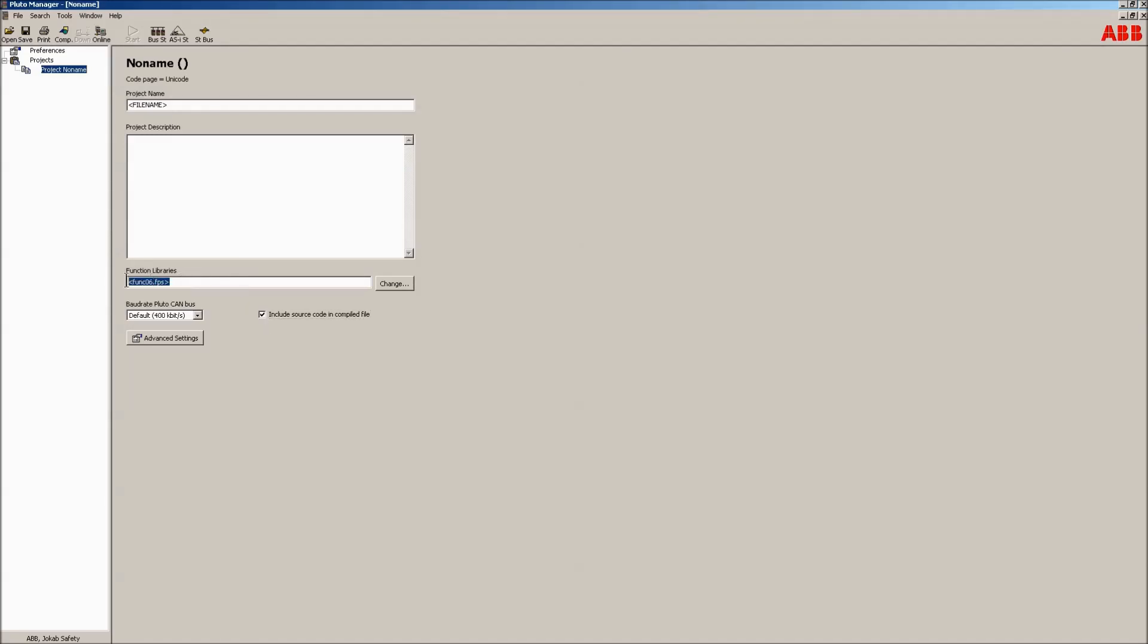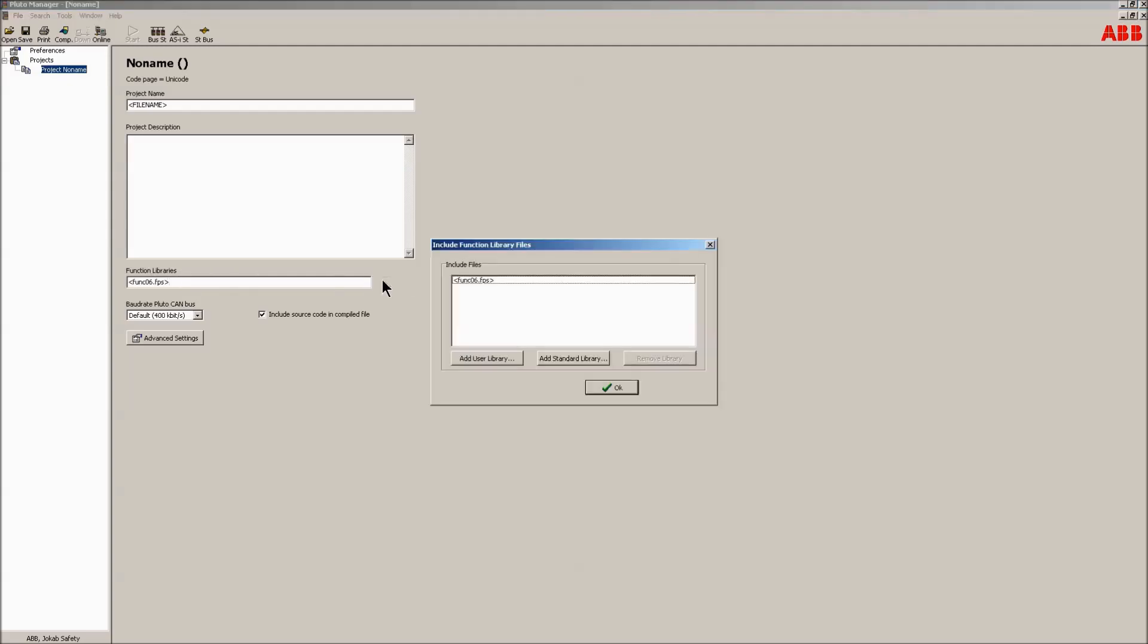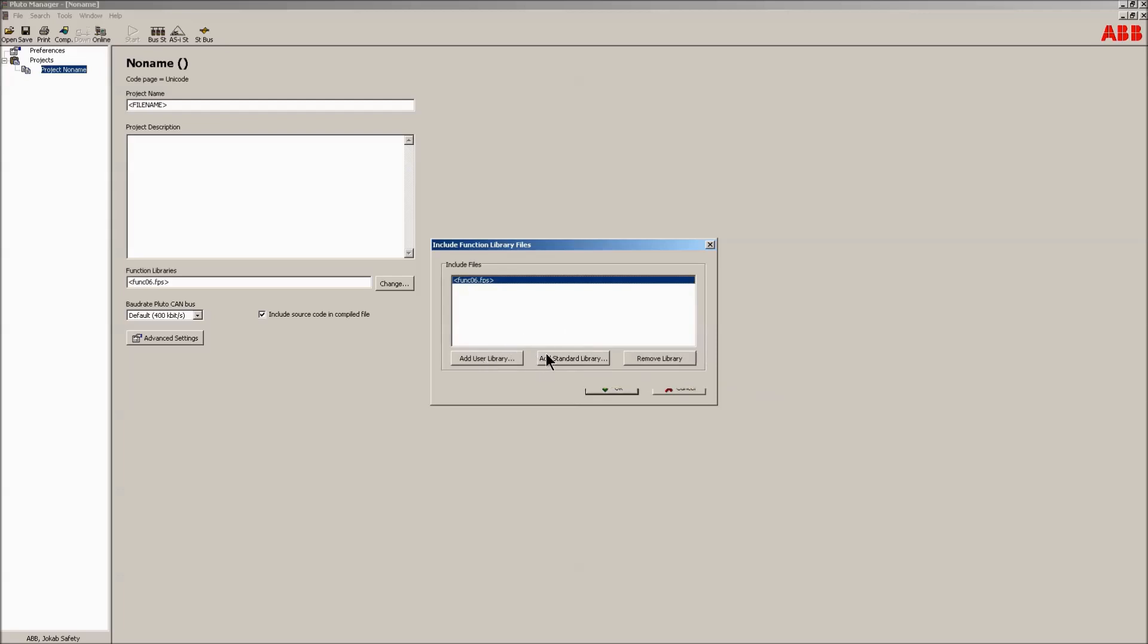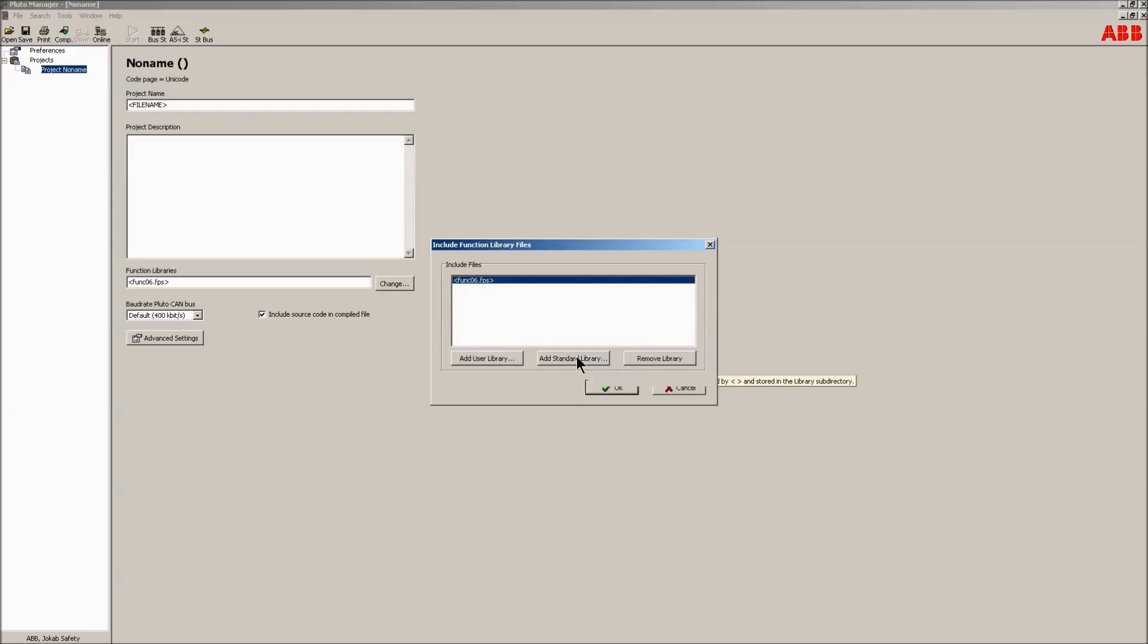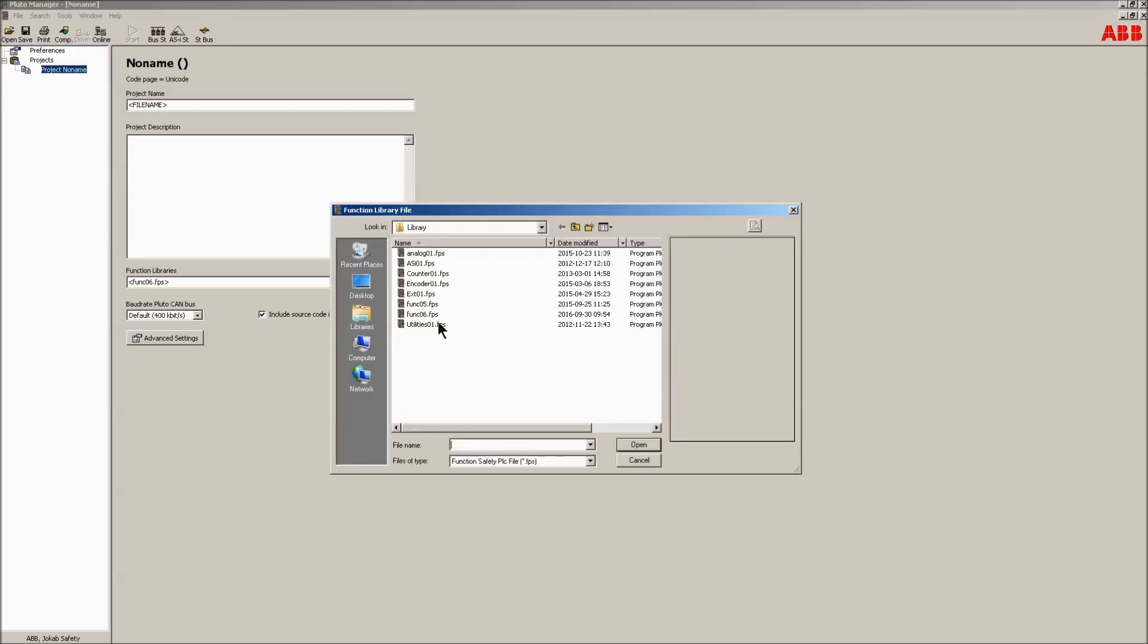The Pluto Manager makes use of function libraries. These libraries contain blocks with TÜV certified code, making it easy to realize safety functions. User libraries can be created, but it's advised to use the standard libraries. There are a number of different libraries, and the library funk 06 is included by default. The blocks inside each library are shown in the right part of the window.